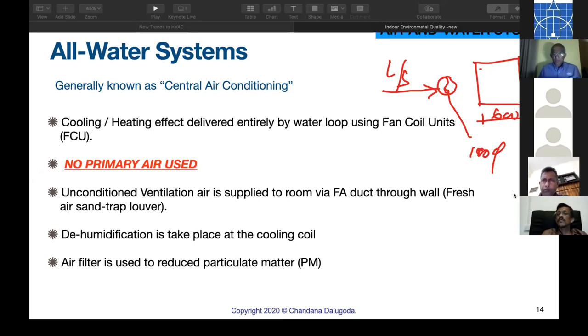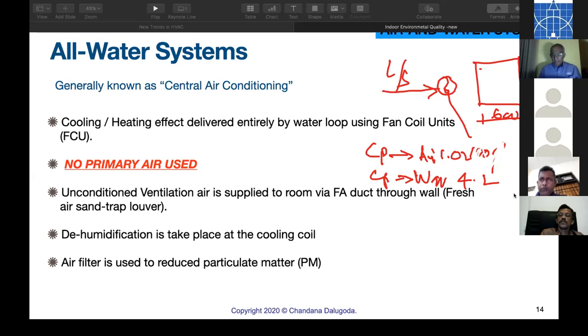Why two cross sections? The air duct is larger, the piping is so small due to Cp, the Cp of air and the Cp of water. 1.0 versus 4.2 is the difference. So water has a higher heat carrying capacity, so smaller pipes. So all water systems benefit in that way. We need only smaller ceiling void space to carry chilled water piping.